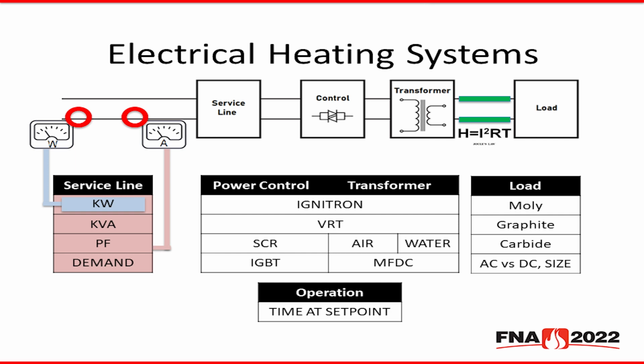And then finally, the most important variable at play is probably the operation, or the time in which you spend the furnace at certain set points. So, for example, when you have a furnace run, do you run at 100% full power the entire run, or do you ramp up to a temperature and then drop your electrical requirements to a plateau? This has a huge impact on the power quality and quantity that you find at the upstream service line.